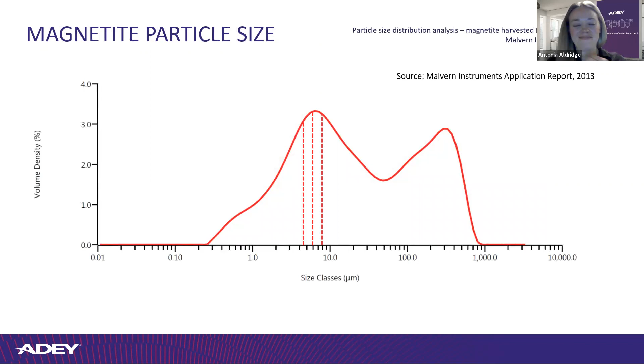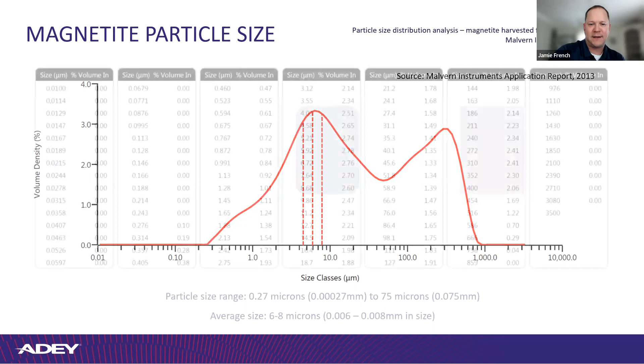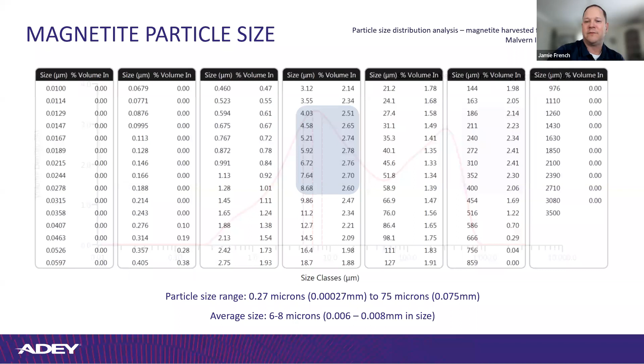Here's the magnetite particle sizes. You can see that hump there is right down below 10 micron, and that's the shaded area where the average size of magnetite is 6 to 8 microns. So again, thinking red blood cells, it's tiny, and that's 95% of your system debris is that small.